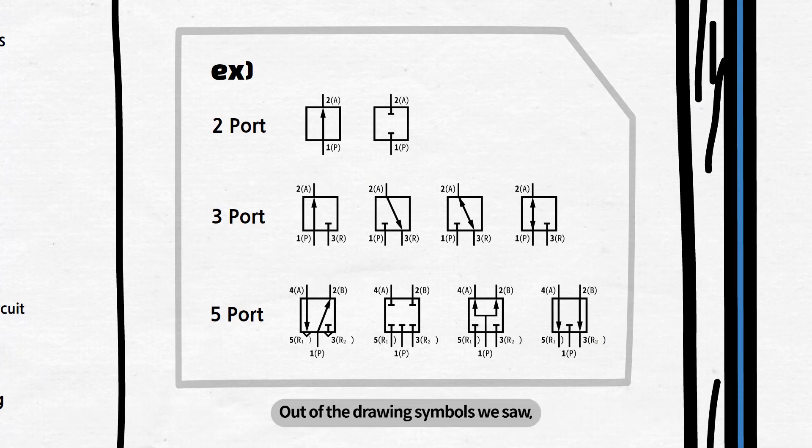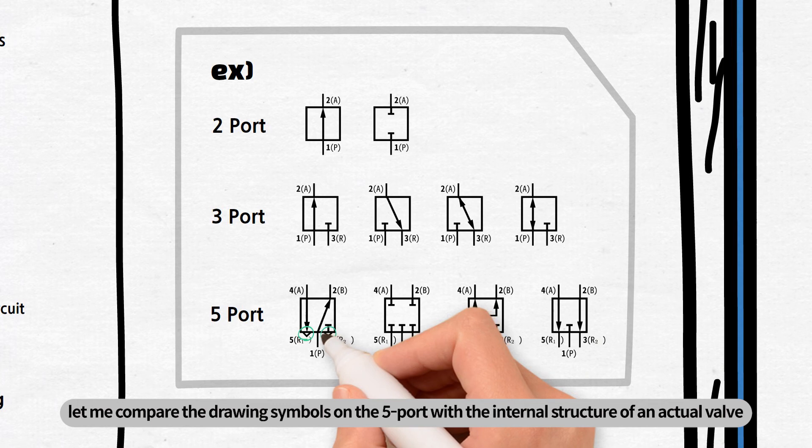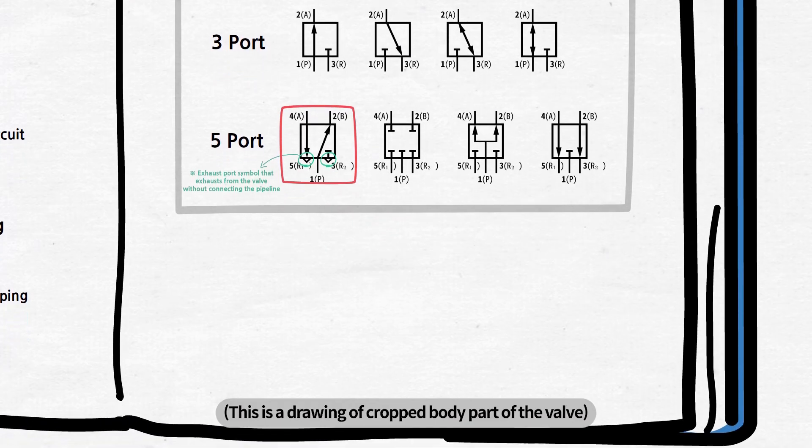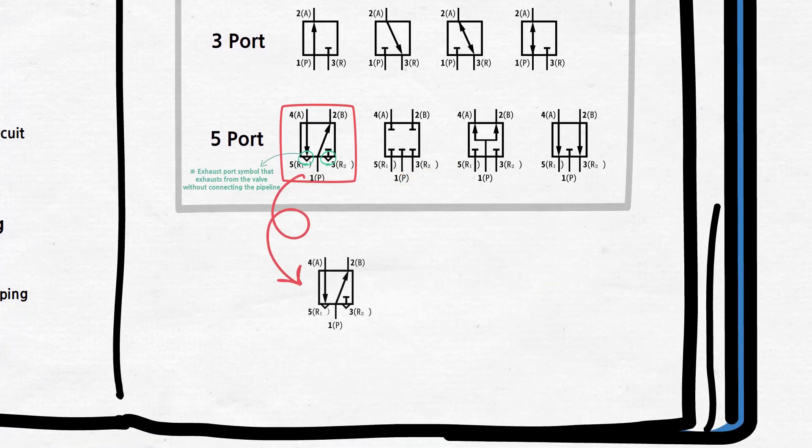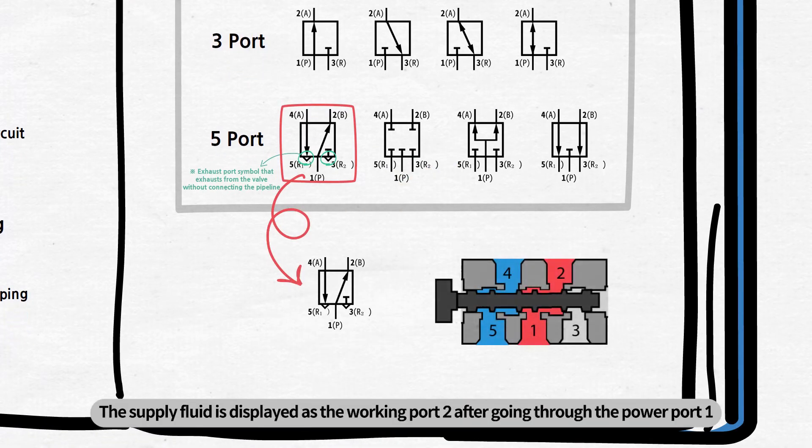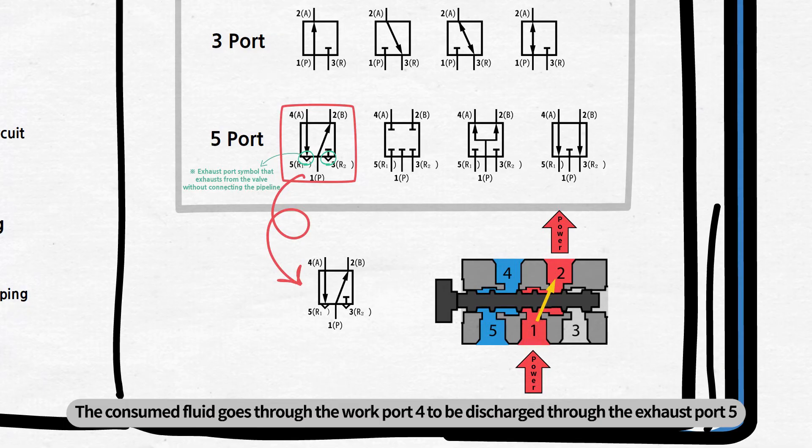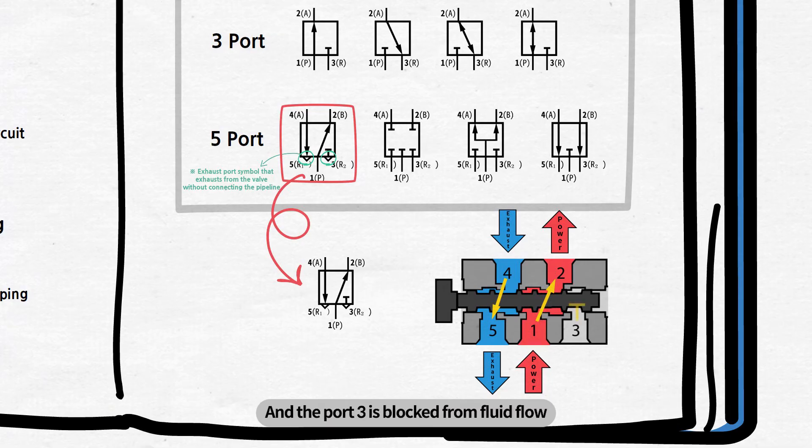Out of the drawing symbols we saw, let me compare the drawing symbols on the 5-port with the internal structure of an actual valve. This is a drawing of a cropped body part of the valve. The supply fluid is displayed as the working port 2 after going through the power port 1. The consumed fluid goes through the work port 4 to be discharged through the exhaust port 5, and the port 3 is blocked from fluid flow.